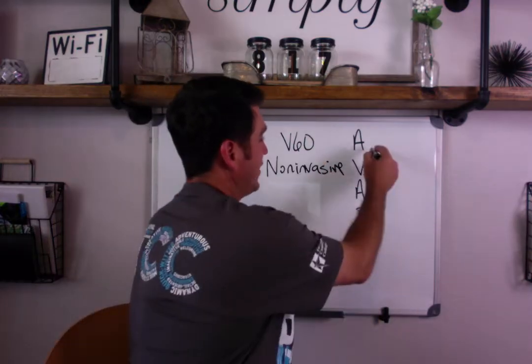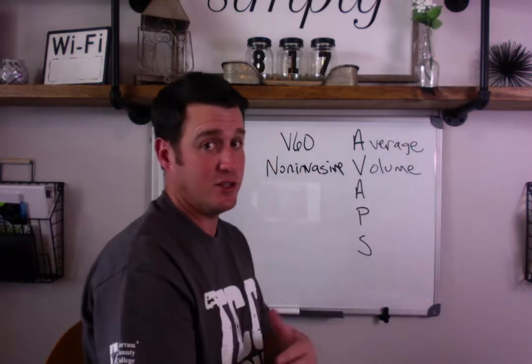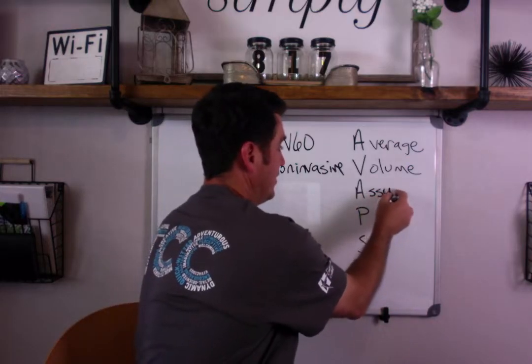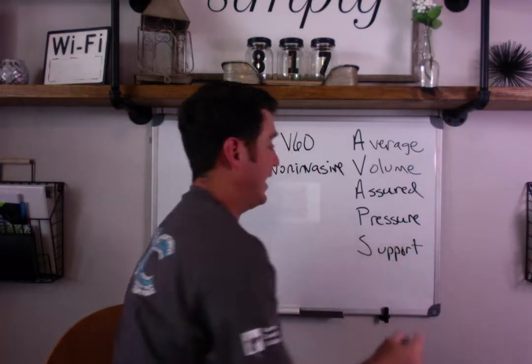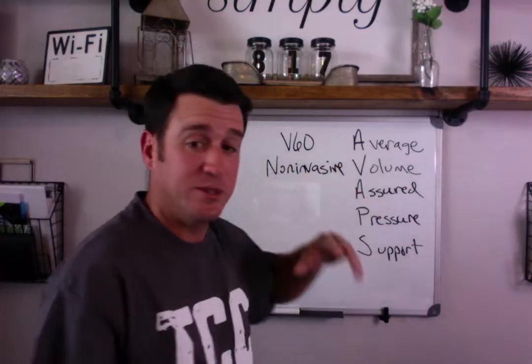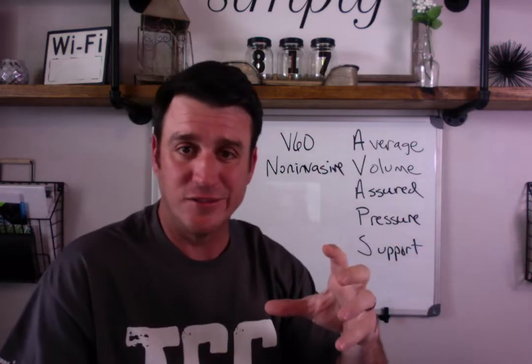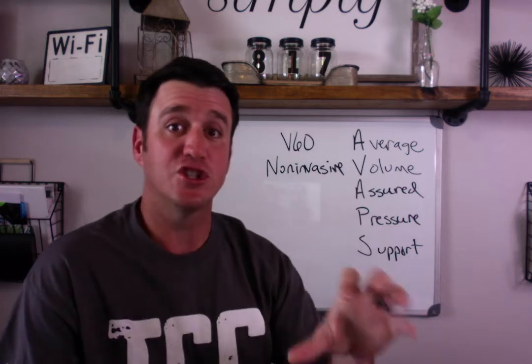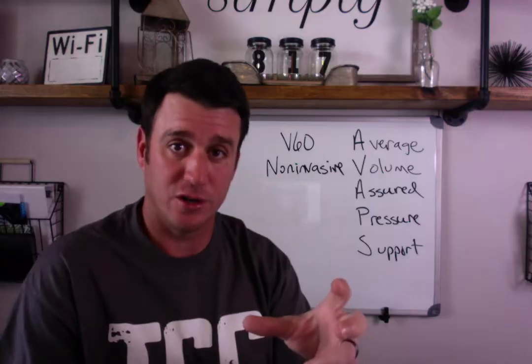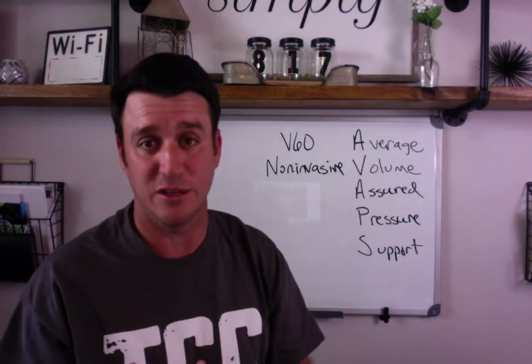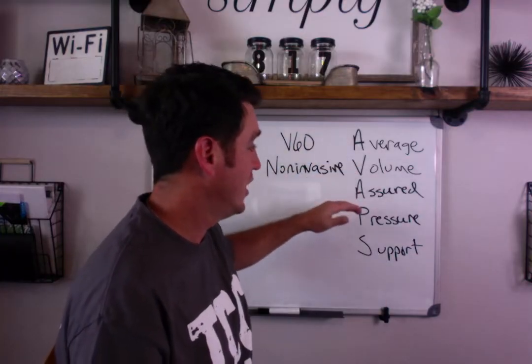So let's talk about what the acronym AVAPS actually stands for. AVAPS stands for Average Volume Assured Pressure Support. Key words there — Average Volume Assured — meaning this is a mode of mechanical ventilation that is going to do its best to assure an average tidal volume. If you can assure an average tidal volume, then you can assure an average minute ventilation, and that's key for what some of these patients need.